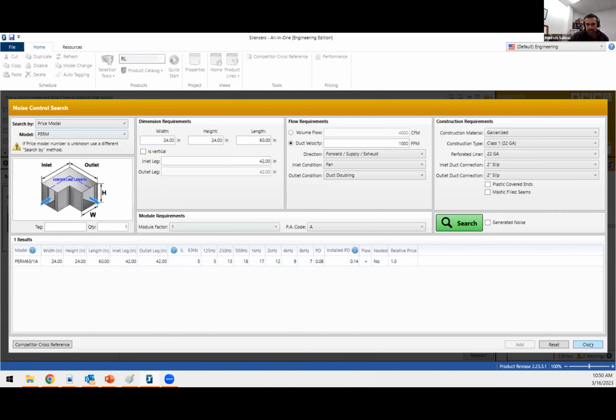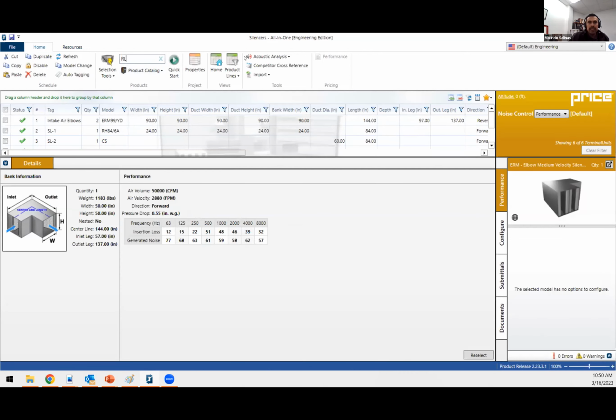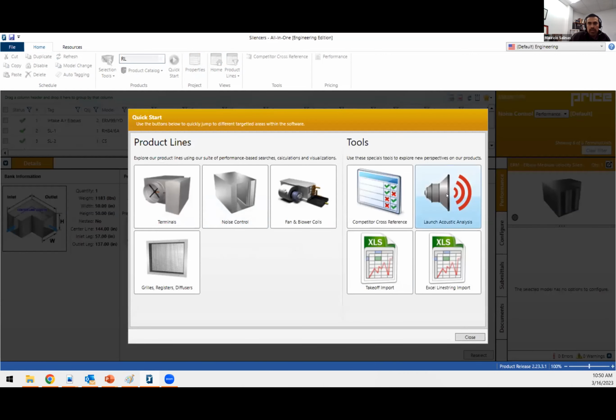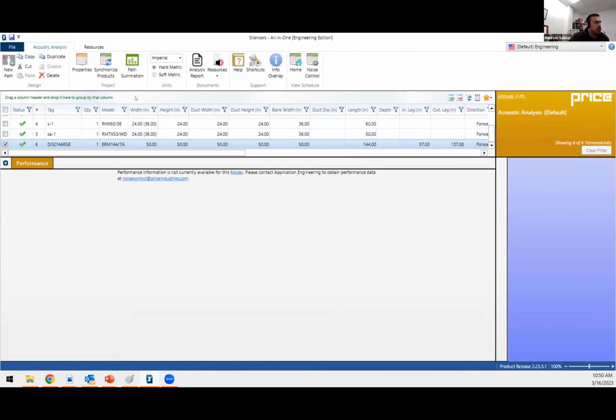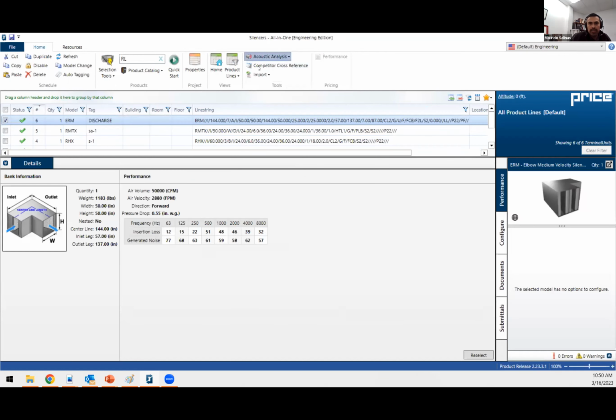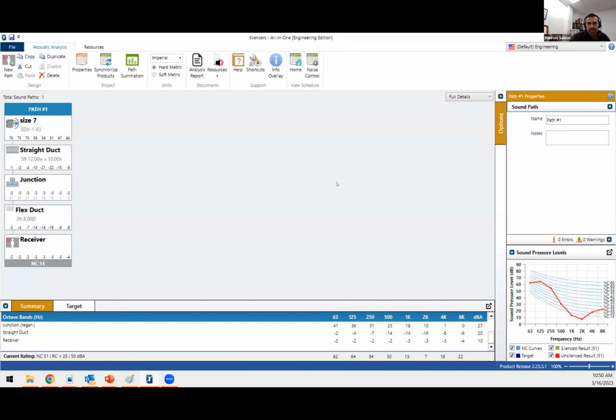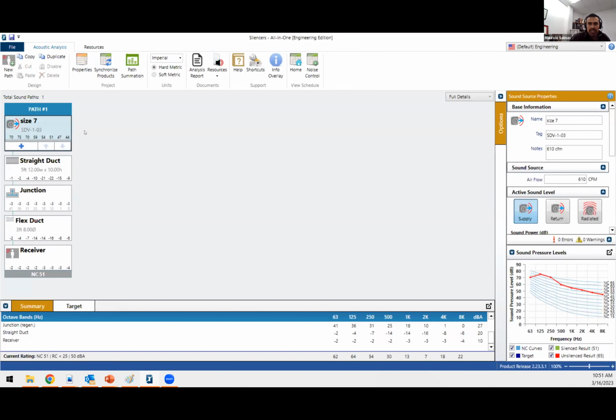Now I have 4 minutes to talk about acoustic analysis. Another way that you could use the software is our acoustic analysis tool here through all-in-one. So let me just go here to acoustic analysis. And what you can use this for is to check real-life conditions, to see if your size 7 SDV 103 that Elizabeth was showing you before is indeed going to meet the NC level in its AHRI 880 rating.